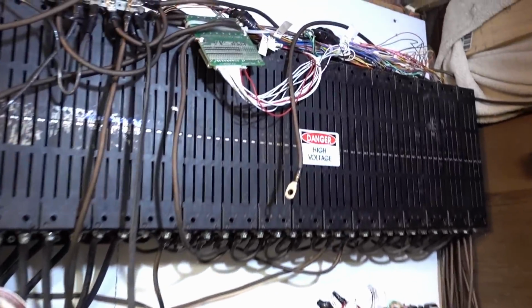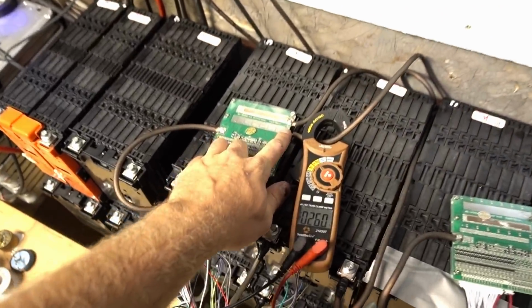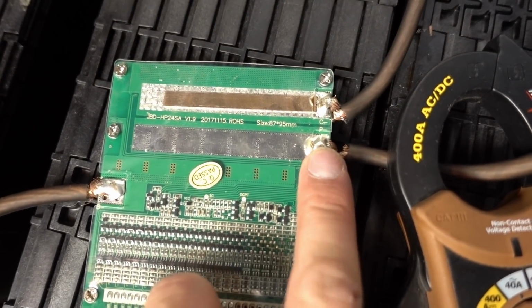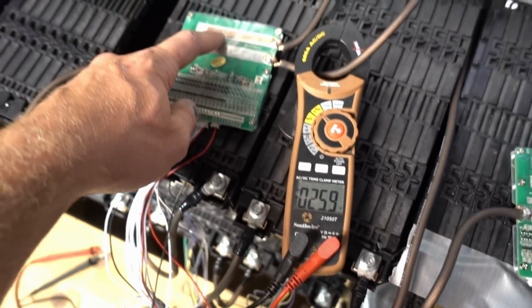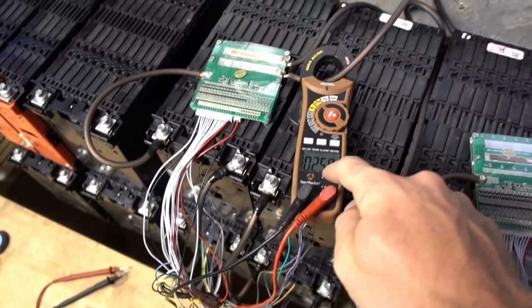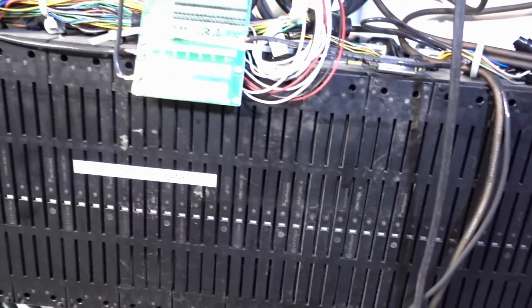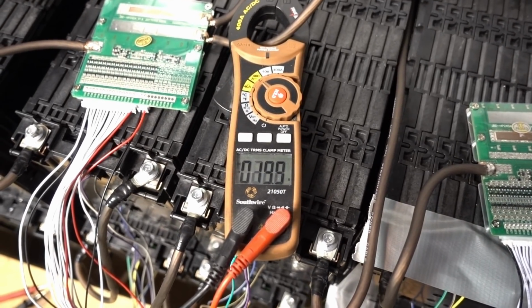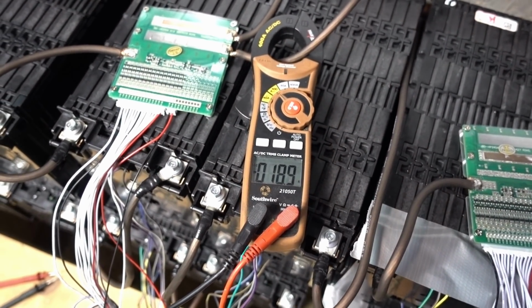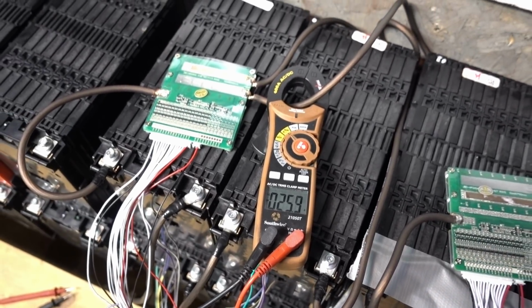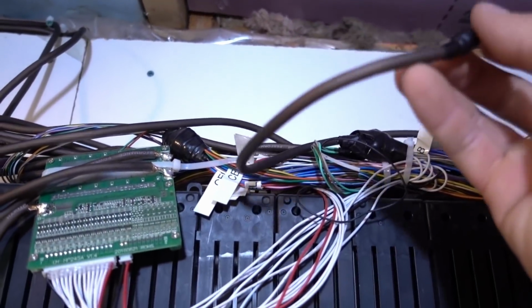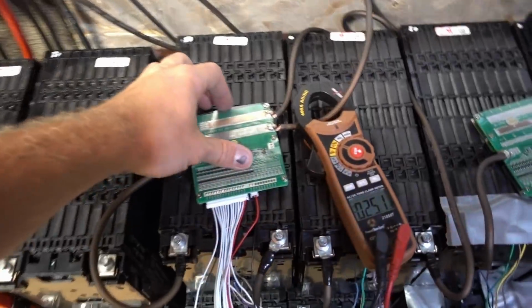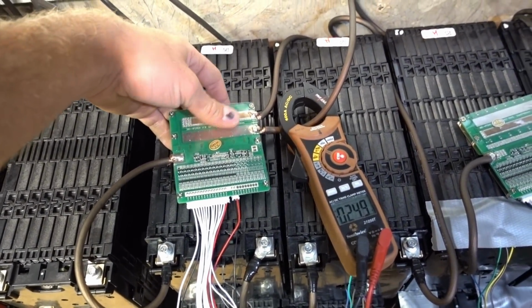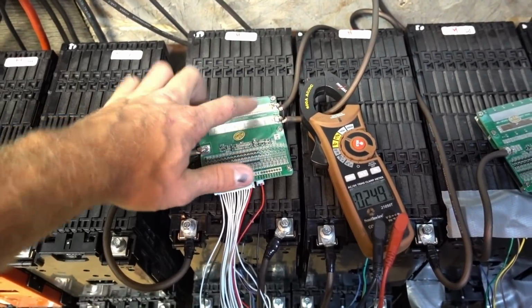Sweet. Now I want to see if I hook up the charge side - right now just the pull side is hooked up. So if I hook up the charge side, will the power flow backwards into the charge side and increase my amperage, because then this will be twice as many strands of wire. We're about to hook it up here, about to find out right now. Wow, it went down - oh yeah, that makes sense though. It went down because part of the current is flowing through this wire, which I don't want because that is the charge circuit. That is very interesting. I know that when this cuts off, it cuts off both of these, so that's good.